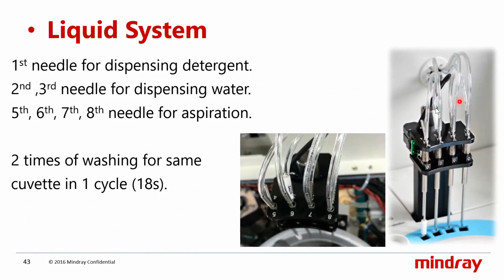So here you can see this wash station clearly. Here you have 3 dispensing lines but 4 aspirating lines. Okay, so one is the first aspiration line, second aspiration, third aspiration, fourth aspiration. Here is the cuvette, and this is the wiper which we discussed, the Teflon wiper, which is going to drain the cuvette and make sure there won't be any water bubbles in the cuvette.